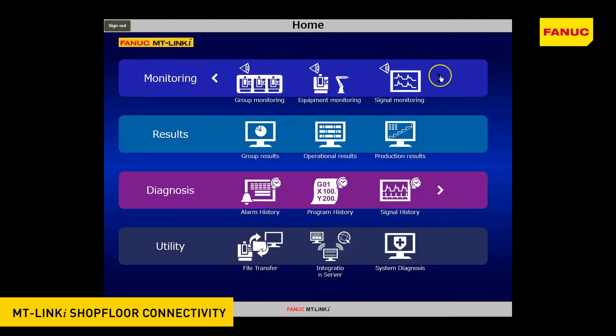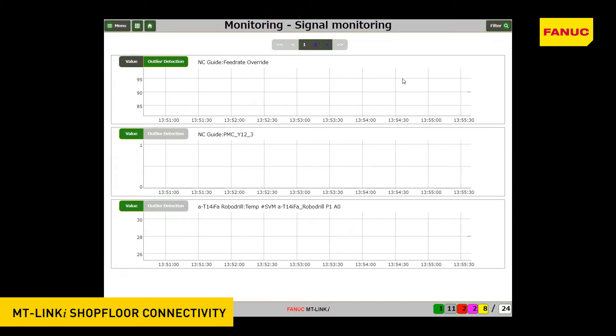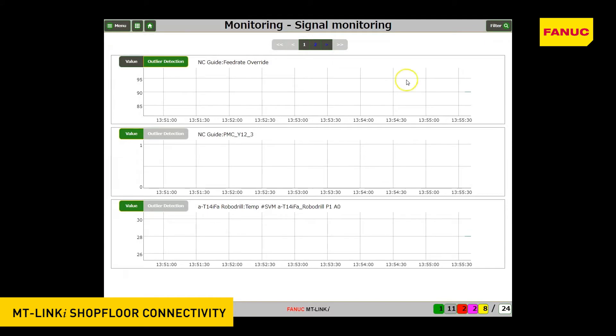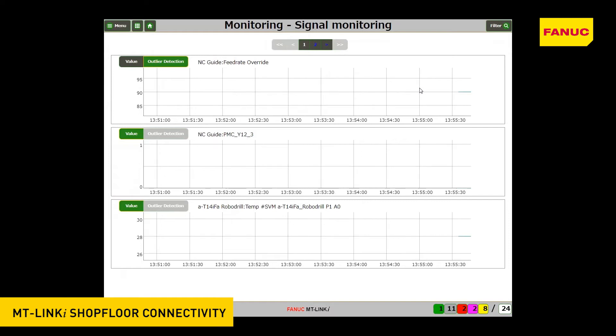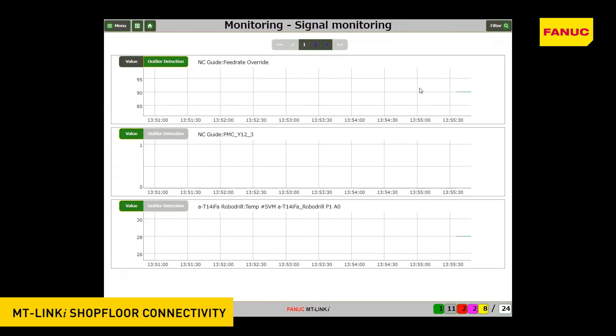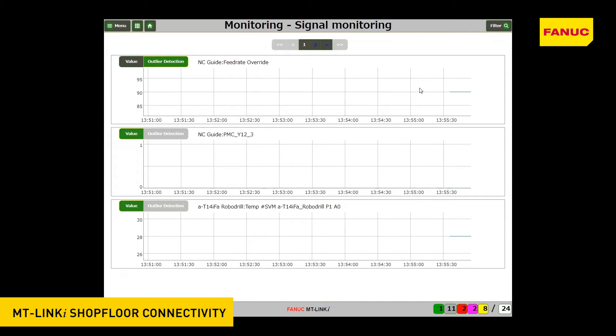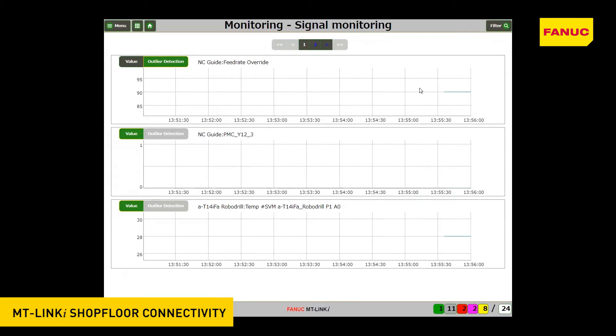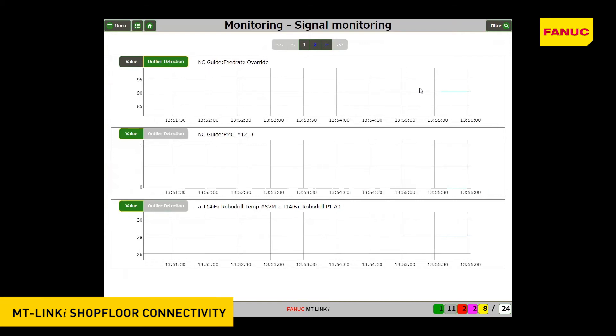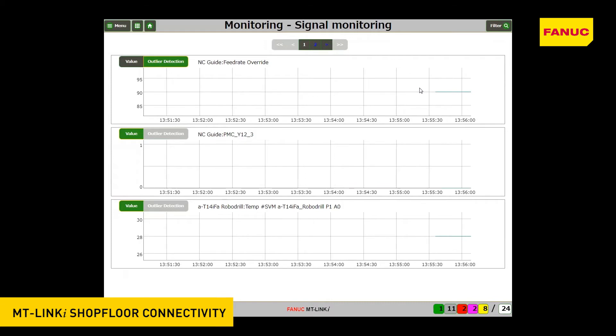Signal Monitoring enables you to monitor in real-time how signals are changing on a selected machine. On the Signal Monitor screen, you can display the status transitions of a length up to 5 minutes and a maximum number of 3 signals on a single screen, allowing you to view simultaneously how correlated multiple signals vary. All of the defined signals and machine status can be monitored. Examples of the easily selectable signals are PMC signals, macro variables, motor temperatures, motor currents, etc.